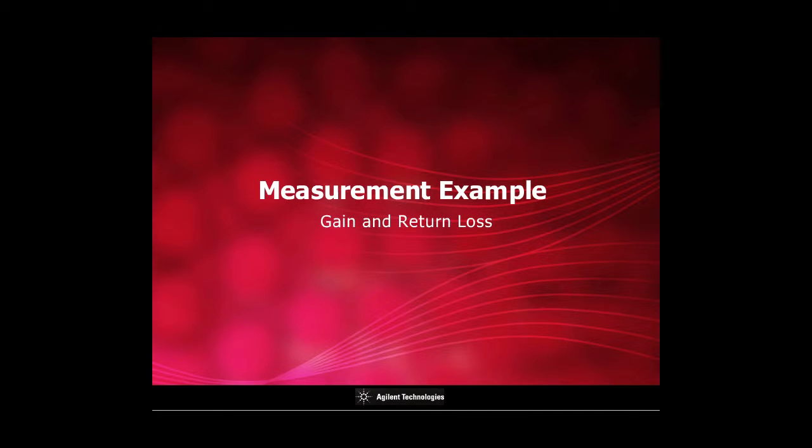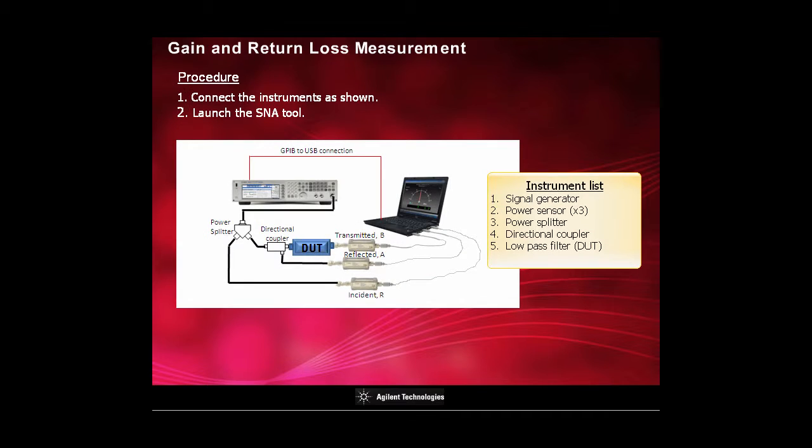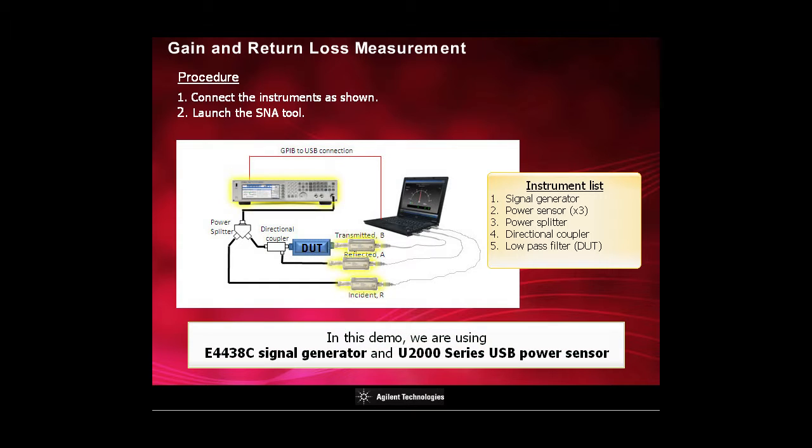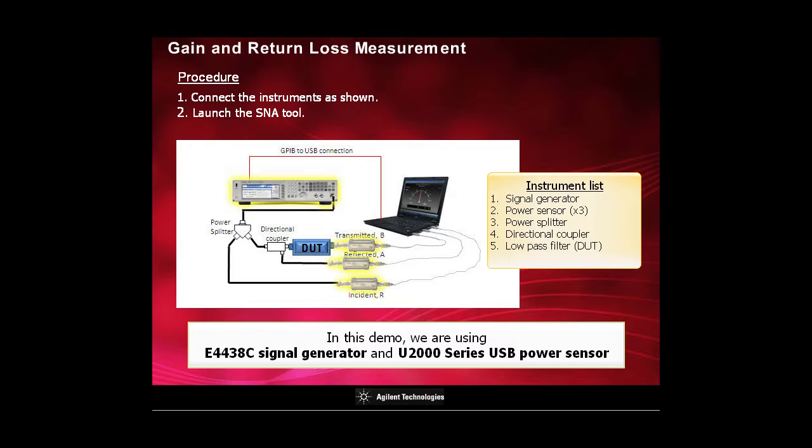In this section, you will learn how easy it is to make gain and return loss measurement. First, connect the instruments as shown and launch the SNA tool. We are using the E4438C signal generator and the U2000 series USB power sensor in this demonstration.